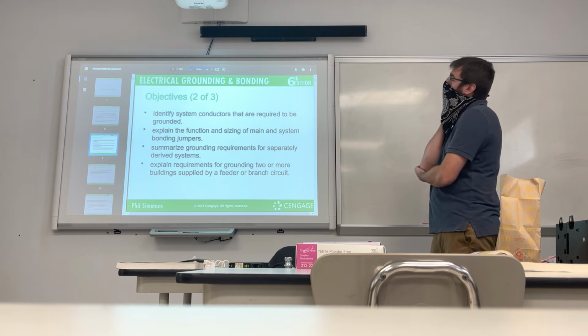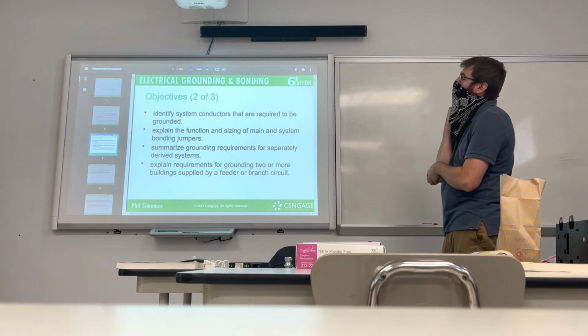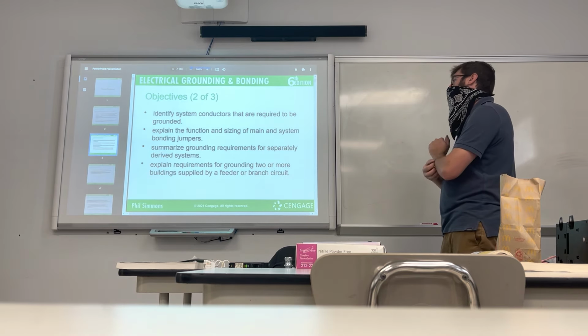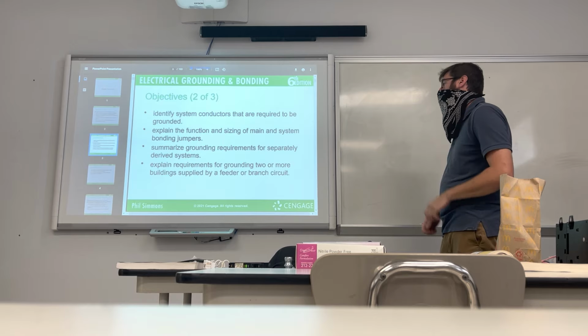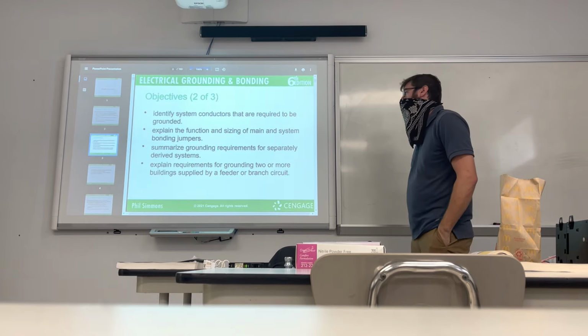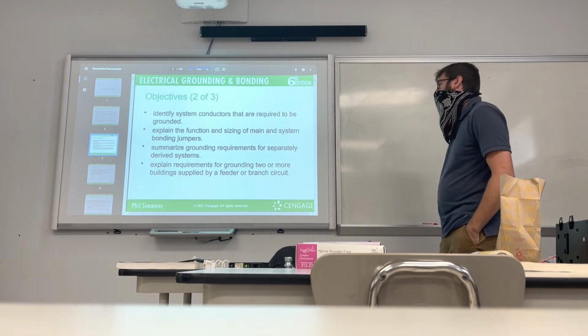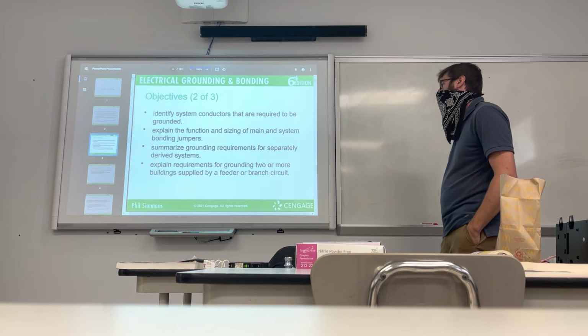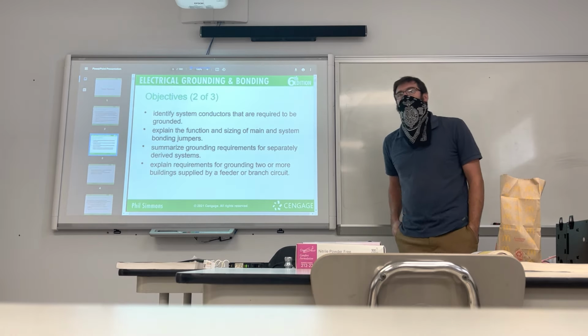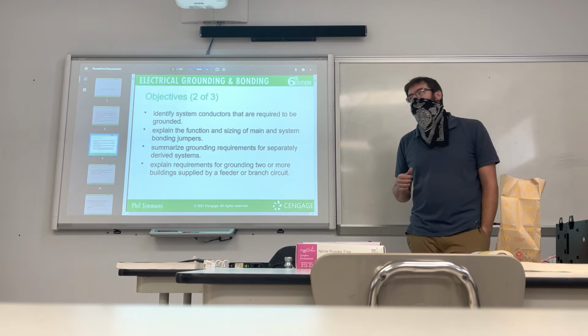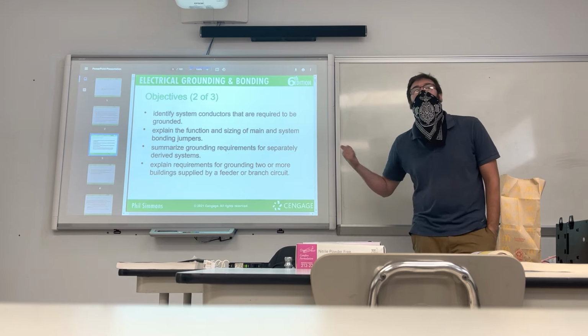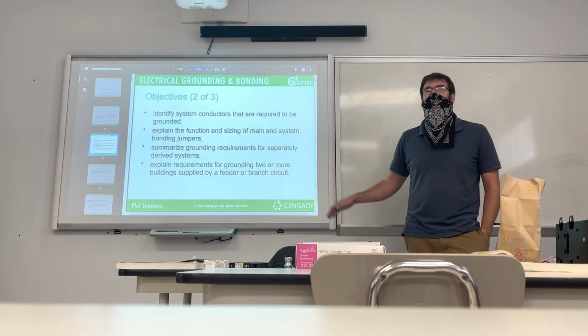Objectives. Identify system conductors that are required to be grounded. Explain the function and sizing of main and system bonding jumpers. Summarize grounding requirements for separately derived systems. Explain requirements for grounding two or more buildings supplied by a feeder or a branch circuit. Now, just for an example, I guarantee you we can talk a couple, we've already spoken about most of these, so we can probably talk about it right here just to see what this says in the slide.